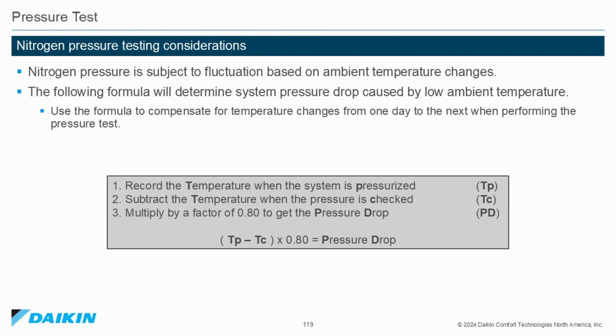Record the temperature when the system is pressurized. Subtract the temperature when the pressure is checked. Multiply by a factor of 0.80 to get the pressure drop. This applies to nitrogen pressure over 300 psi.